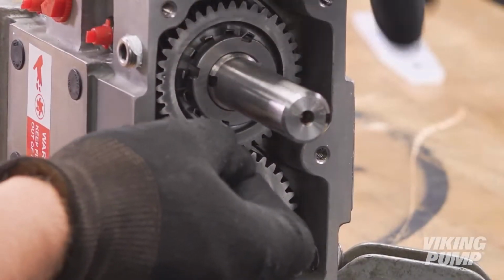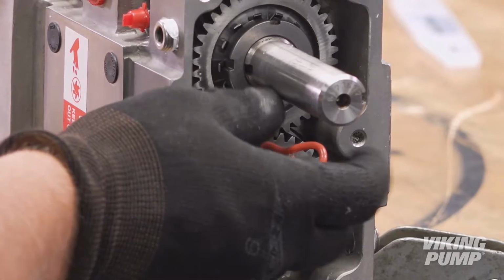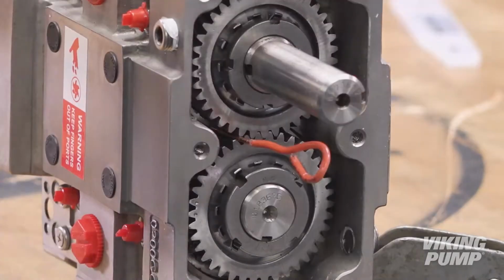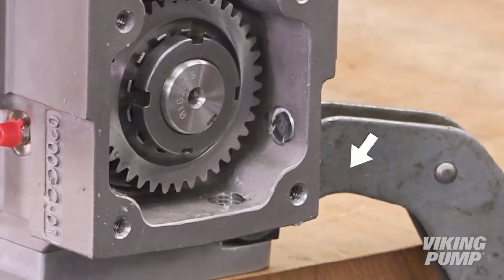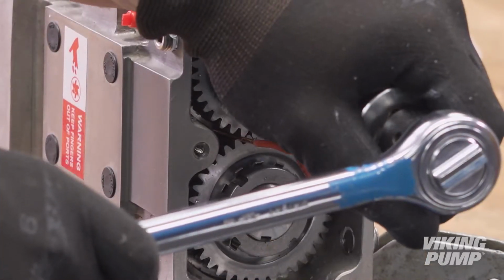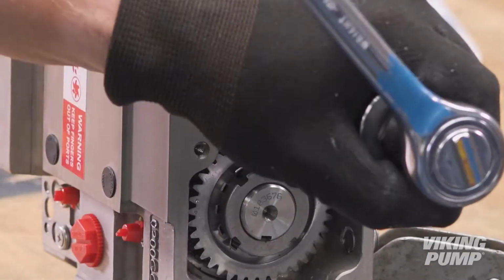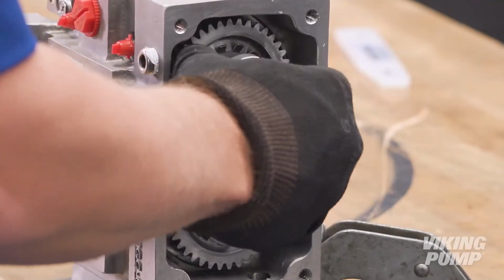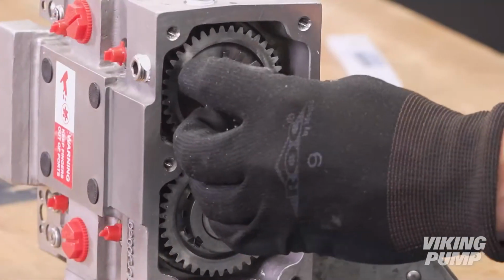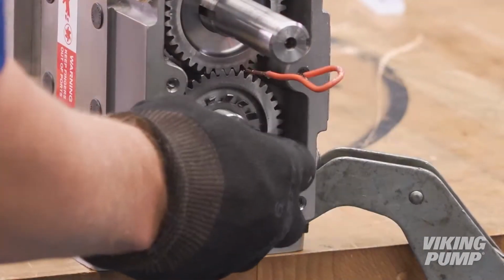To prevent the shafts from turning, place a wooden block or piece of copper wire between the gears. The pump may be clamped to the bench to further aid with lock nut removal. Use a lock nut tool, hook nose spanner wrench, or punch to remove each lock nut and lock washer. The shaft ends can be wrapped in tape to protect the keyways and splines throughout disassembly.